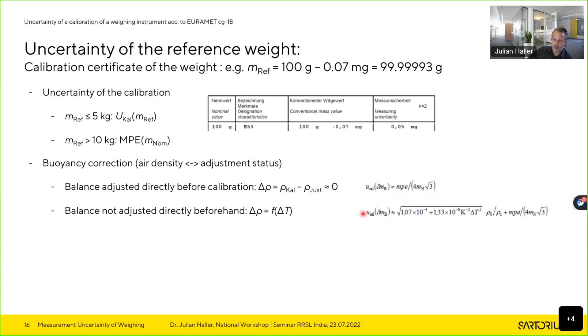The next contribution to the uncertainty of the reference weight is that you may have had this weight calibrated, I don't know, 6, 12, whatever months ago. And of course, if you use a weight, it will change the true value. So you have to take that into account. And this is usually based on experience. If you know that usually your weight drifts or changes by this amount between two calibrations, then you have to take that into account for the uncertainty of your weight. This is the experience of the owner of the weight; for us as a calibration lab for weighing instruments, it is based on the experience we have with the analysis of changes of our weights.